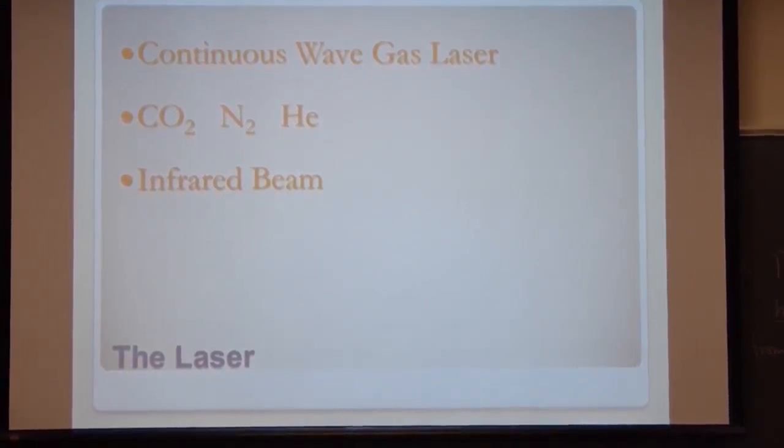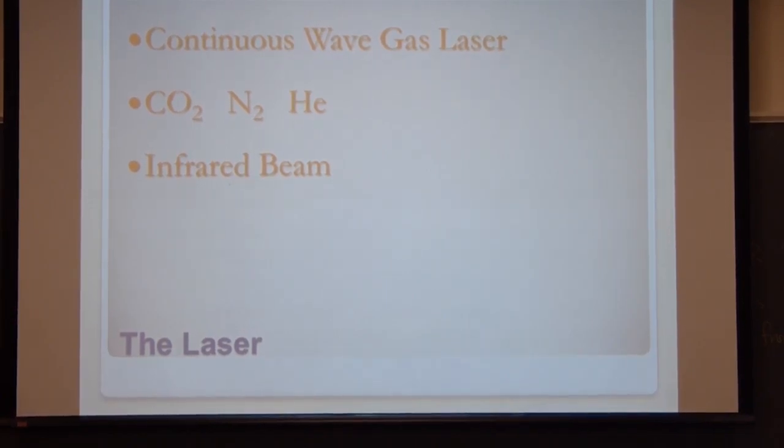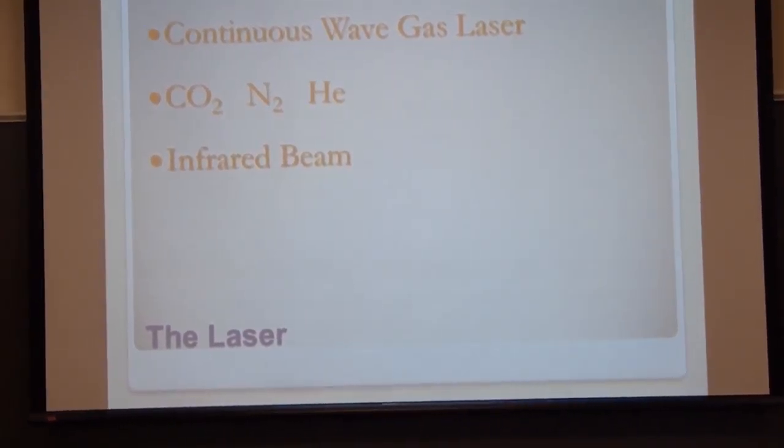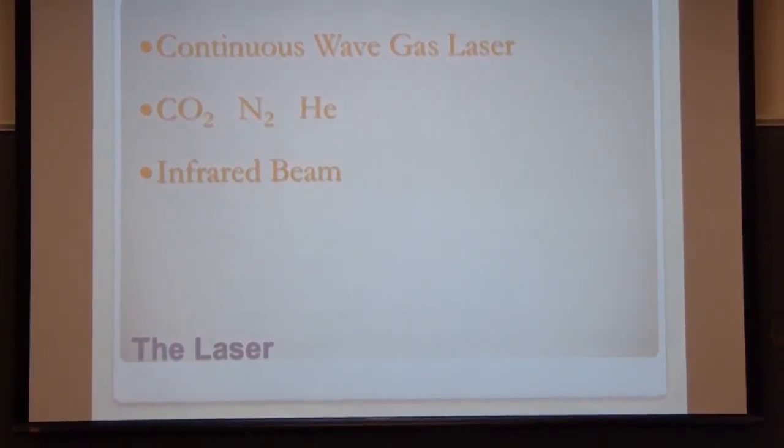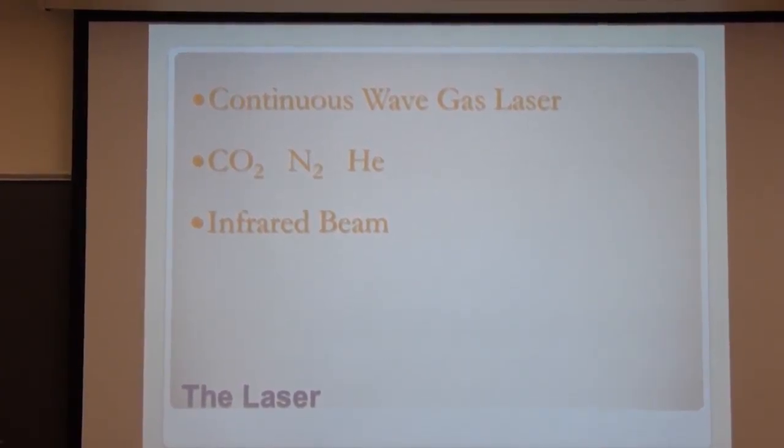It uses a mixture of carbon dioxide, nitrogen, and helium, and that gives us an infrared beam. It lases at 10.6 microns, which, just to give you sort of an idea, we end up with like 300 to 400 degrees Celsius peak temperatures with that.